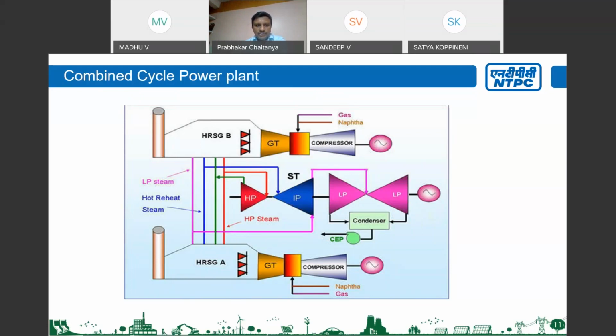So we use other sources like HRSG, heat recovery steam generator. We have two gas turbines here, and whatever flue gas comes off the gas turbine is let into a heat recovery steam generator. It is similar to a boiler, but here combustion won't take place; only the heat from the leftover flue gas is used to convert water into steam.